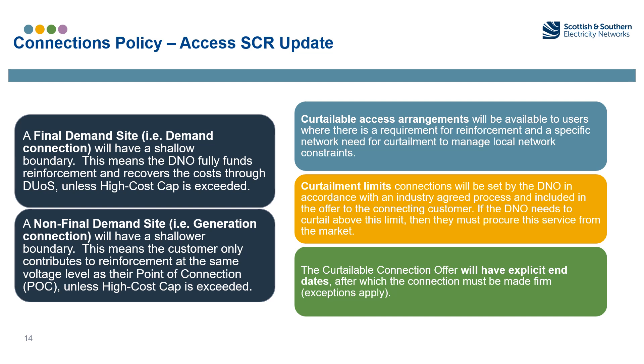SSEN will also provide a curtailment limit. Curtailment limits for connections will be set by the DNO in accordance with an industry agreed process and included in the offer to the connecting customer. If the DNO needs to curtail above this limit, then they must procure the service from the market. The curtailable connection offer will have an explicit end date, after which the connection must be made firm — meaning transferred over to a non-curtailable connection.